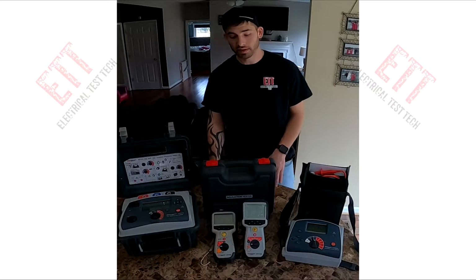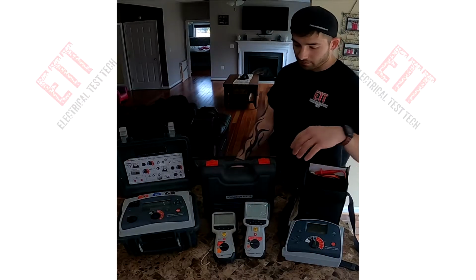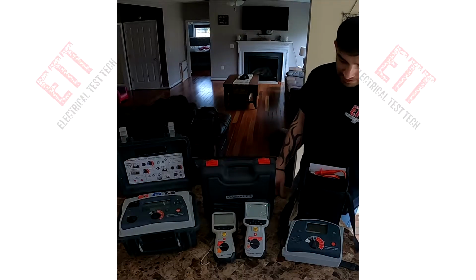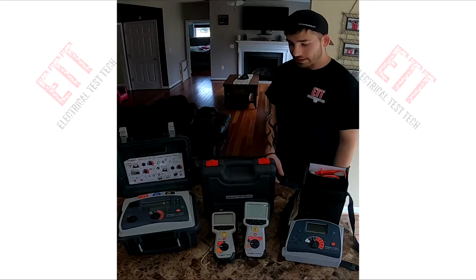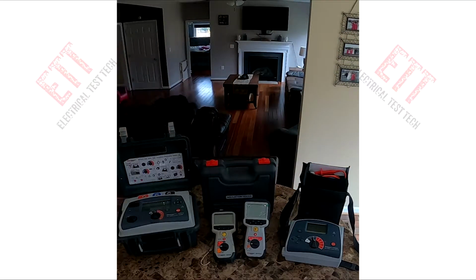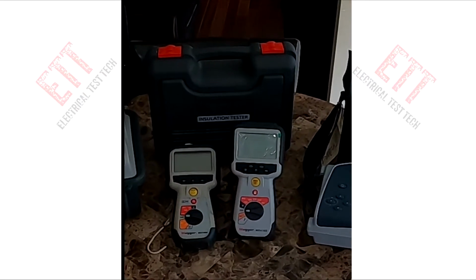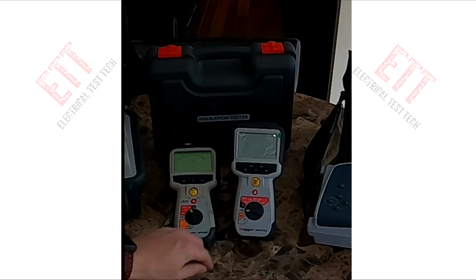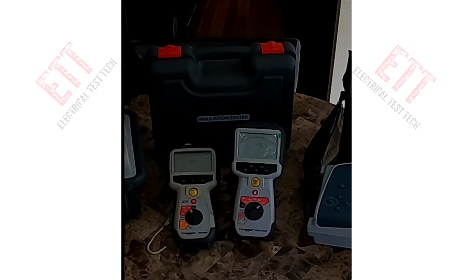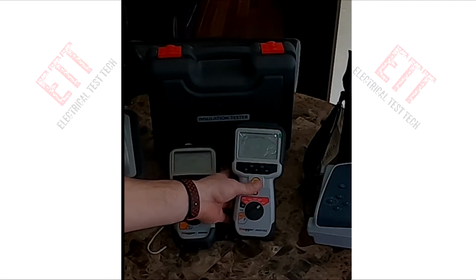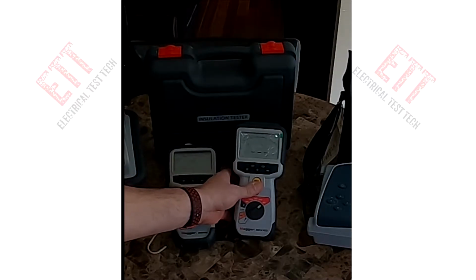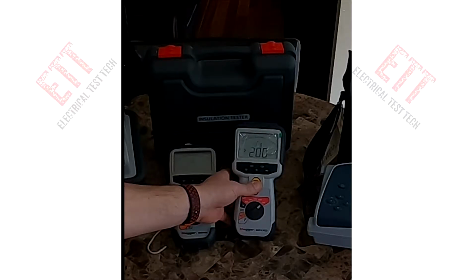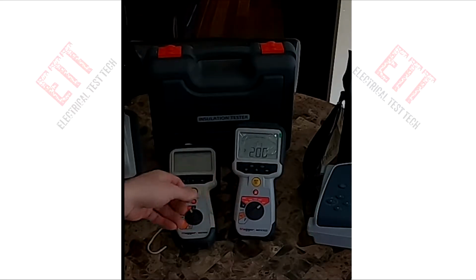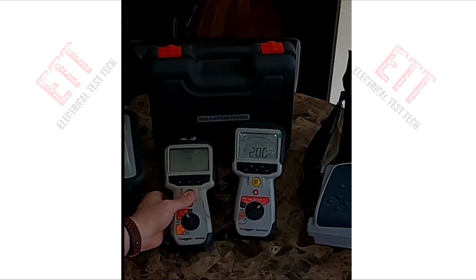Let's start with the two 1,000 volt Meggers here in the middle. I've got a MIT 400 and an MIT 410/2. Slight difference between the two of them, one being the max range scale of each one. They both go to 1,000 volts. This has the extra 50 and 100 volt steps. But this one, you'll see, will go to 200 gig ohms, whereas this one here goes to 20.